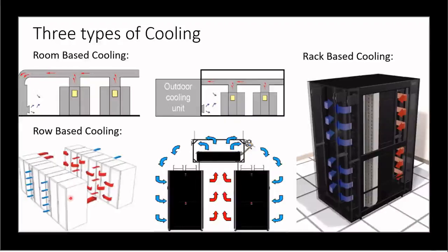Now the row based cooling. In a data center there are lines of rows, row 1, 2, 3, 4, and here's how they categorize this side. They generate hot air, and that hot air flows through here. This is a CRAC unit, computer room air conditioning unit. The hot air flows through here, refrigerant cools it, and cool air flows through these racks. This is rack based cooling.